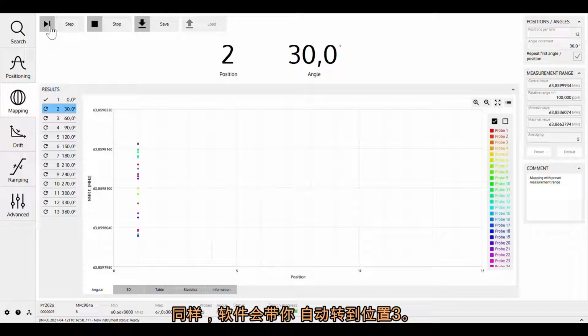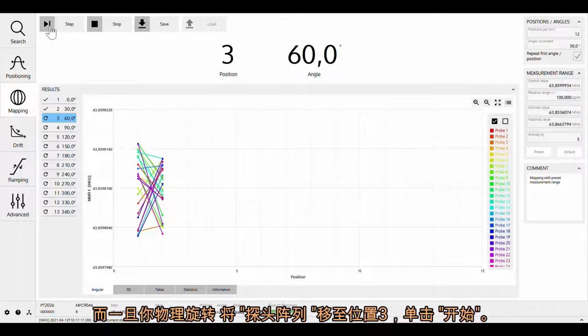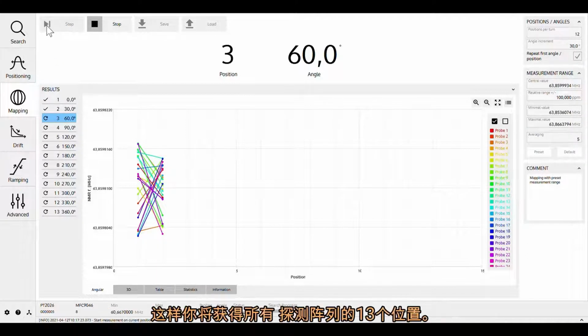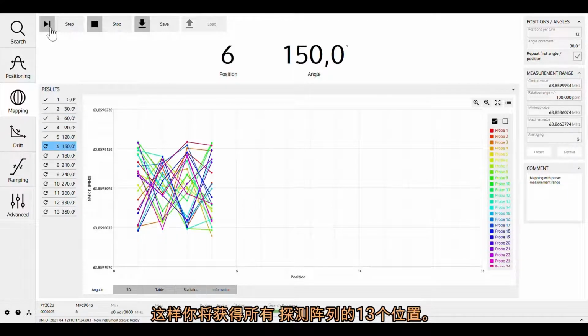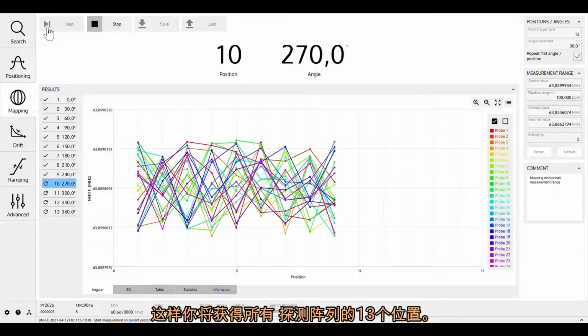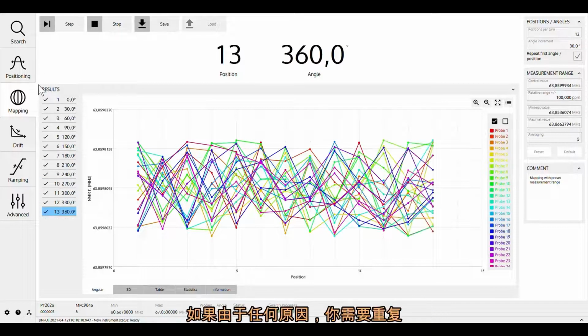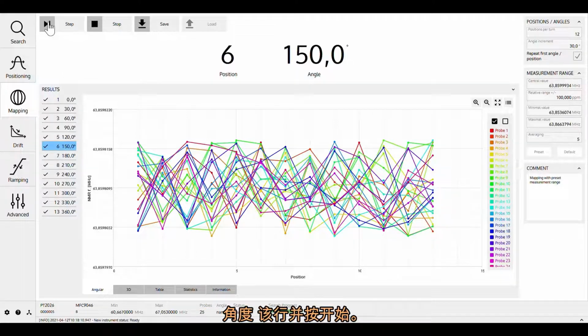Again, the software takes you to position 3 automatically, and once you have physically moved the probe array to position 3, click Start. This way, you will acquire all 13 positions of the probe array. If for any reason you need to repeat an angle, highlight that line and press Start.